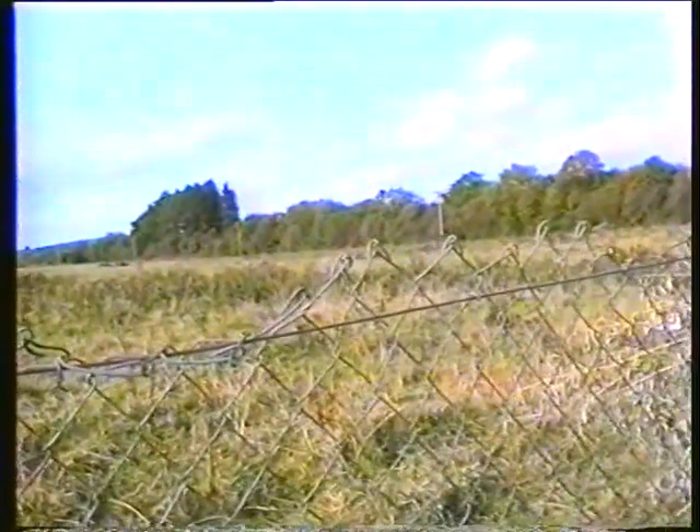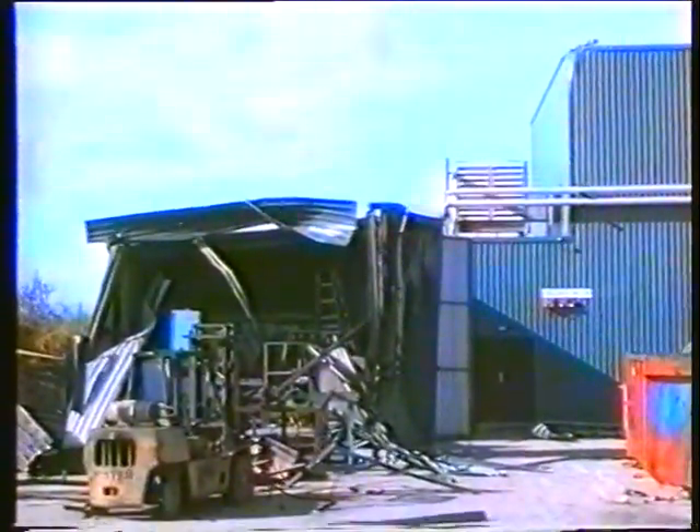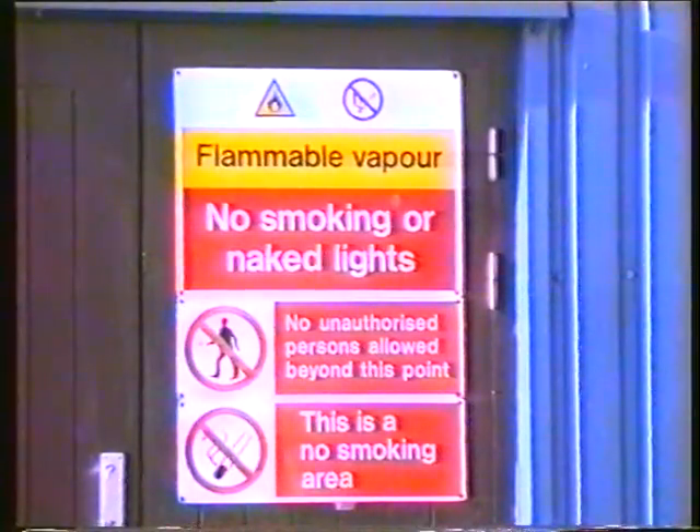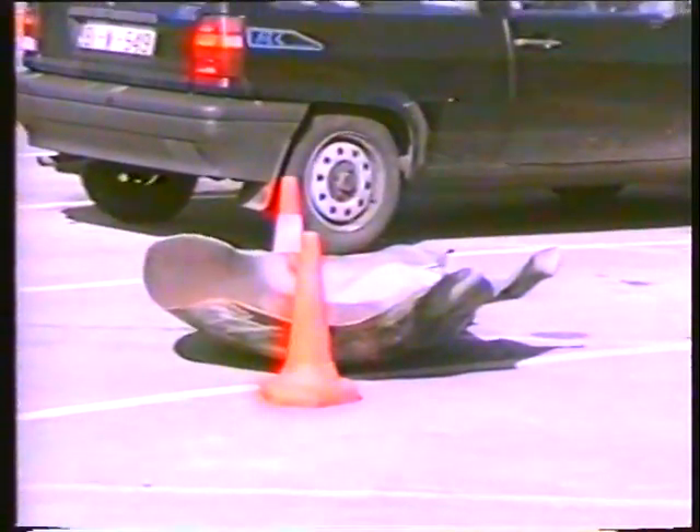The half tank section, trailing fire like a rocket, has disappeared over the trees in the distance. Here we see the damaged machinery store and the high level contact with the building holding highly flammable chemicals. The dished end has travelled about 150 metres into the empty car park of the manufacturing complex next door. The tank midsection has turned into a flat sheet of plate close to the point of contact with the building.